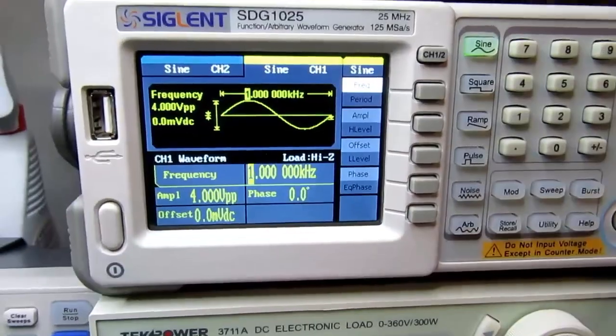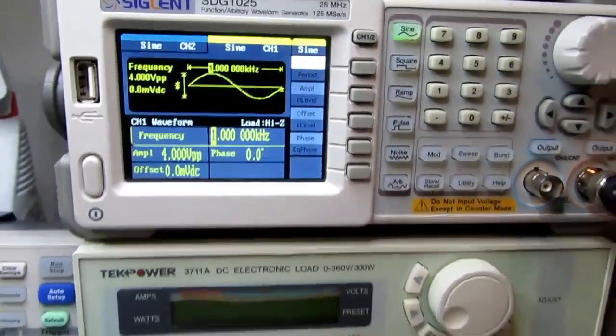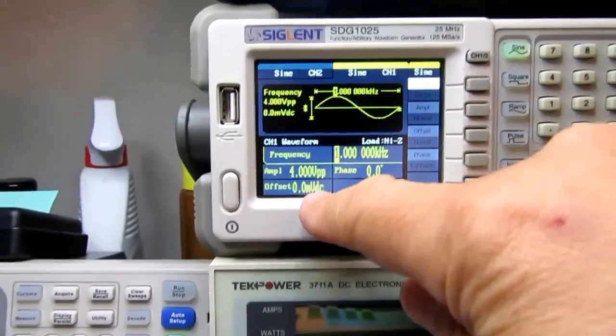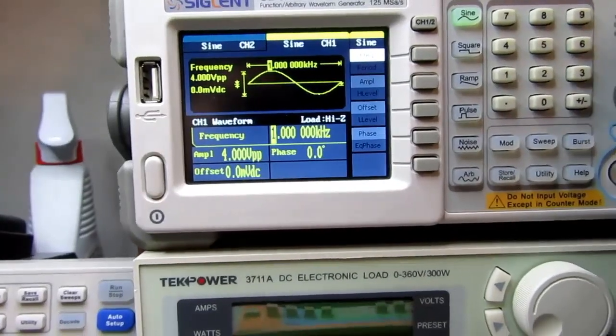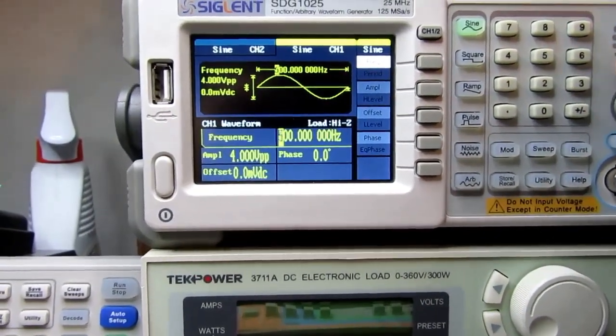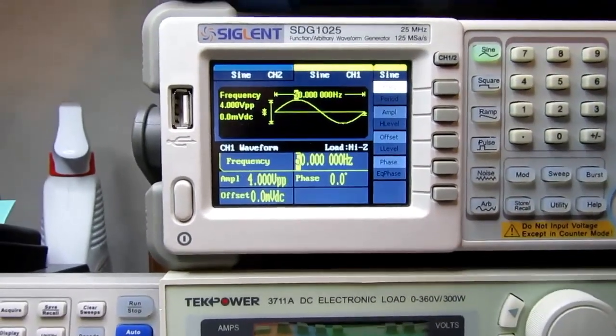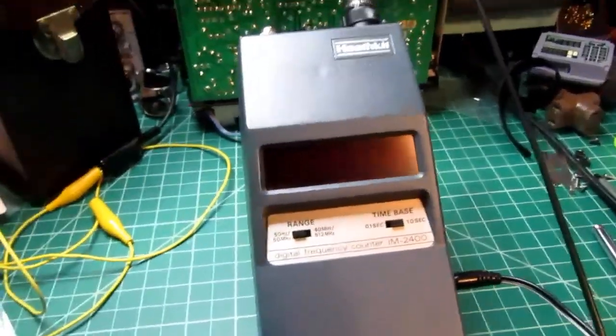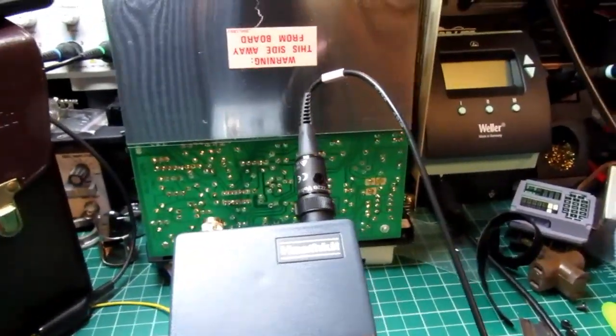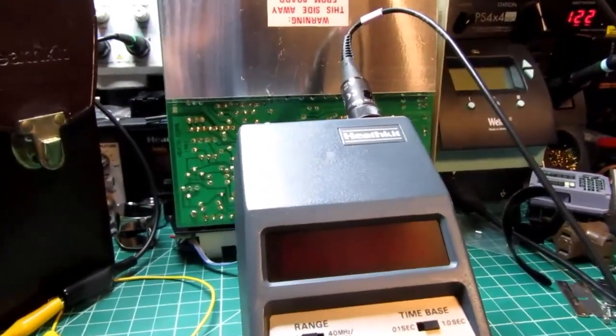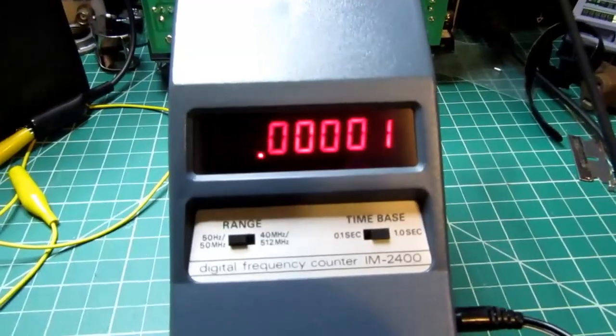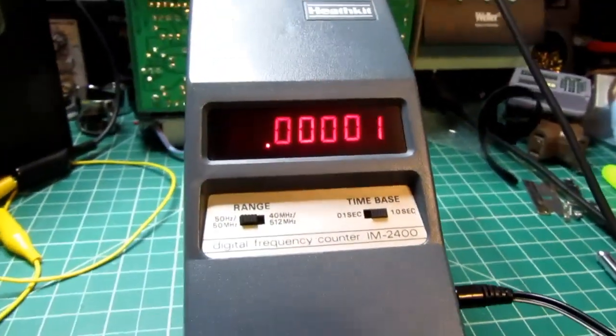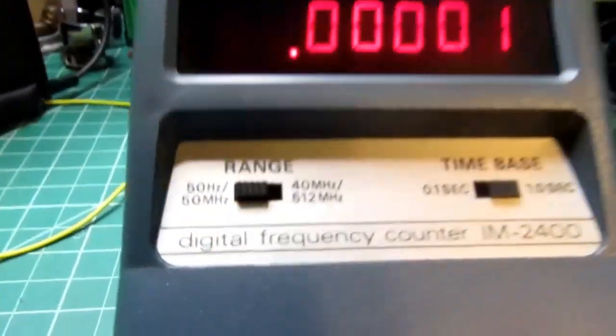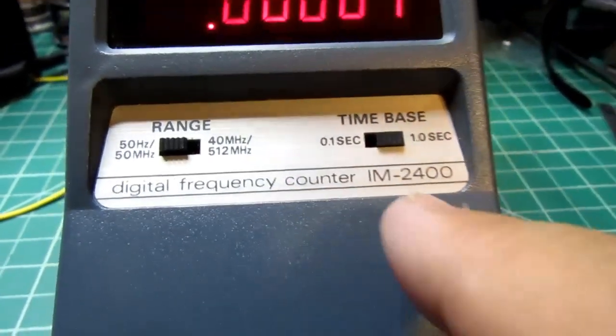And so I've got the power supply plugged in. I have a Siglent function generator here, which I'm going to crank down. I've got it set up for 4 volts peak to peak right now, and I'm going to crank that down to the lowest frequency that this machine is capable of reading, 50 hertz. So I'm going to turn the unit on. This is still turned off, and there I get a nice display. It's basically sitting at 0. I have it selected to the 50 hertz to 50 megahertz range, and I have the time base set to 1 second.